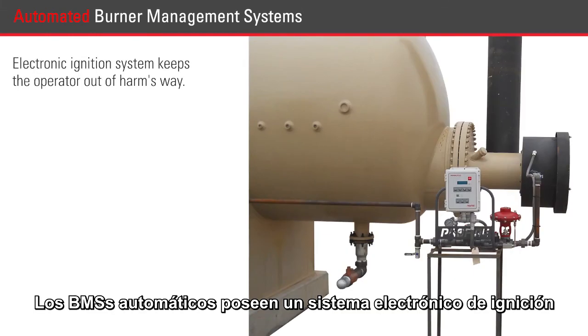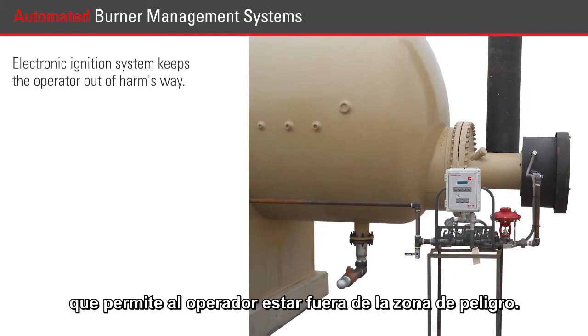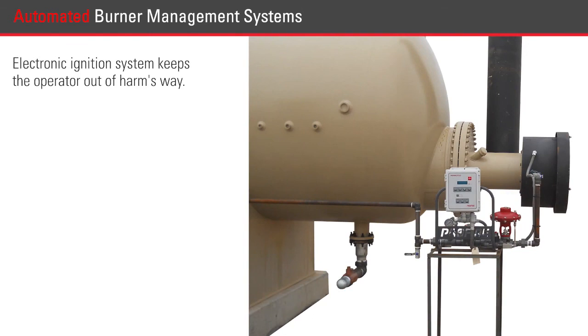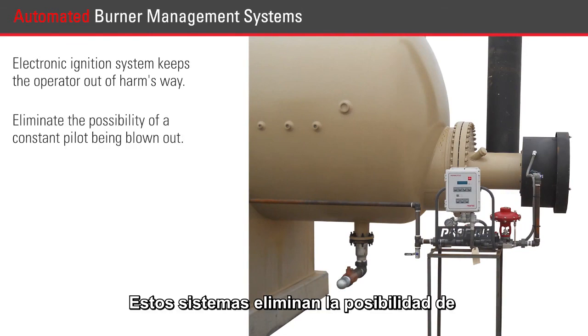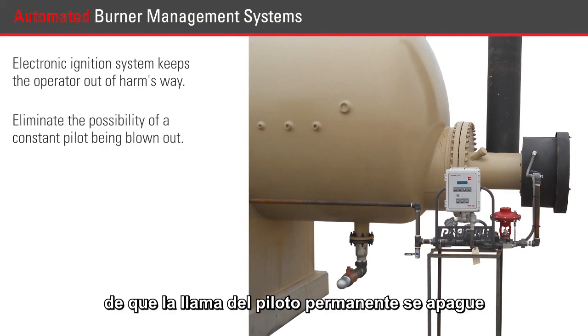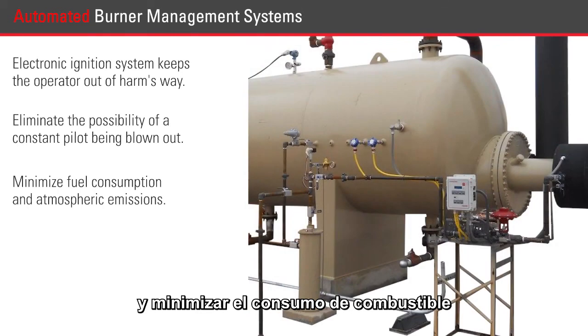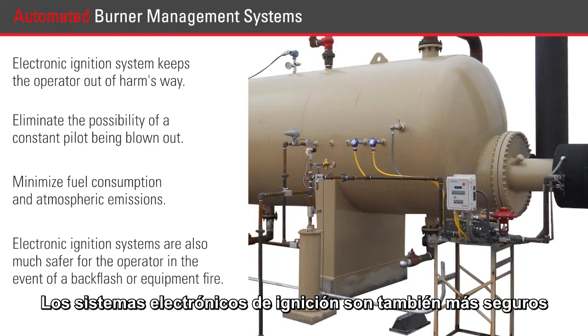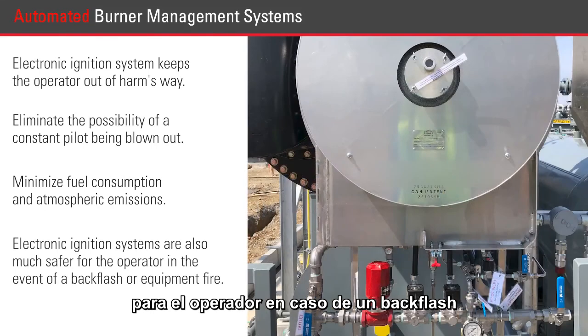Automated BMSs will have an electronic ignition system that keeps the operator out of harm's way. These systems eliminate the possibility of a constant pilot light being blown out and minimize fuel consumption and atmospheric emissions. Electronic ignition systems are also much safer for the operator in the event of a backflash or equipment fire.